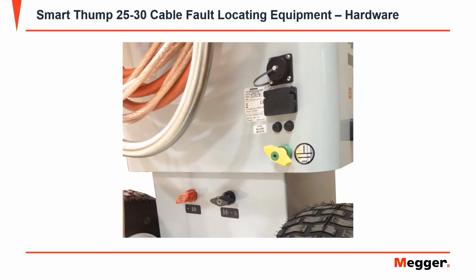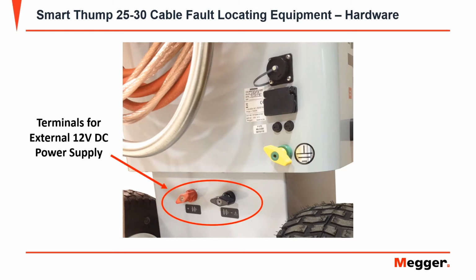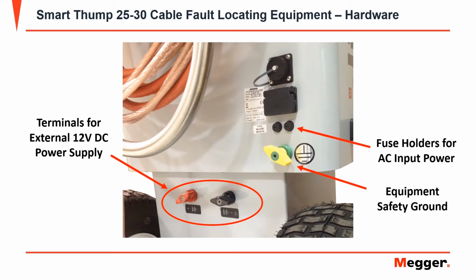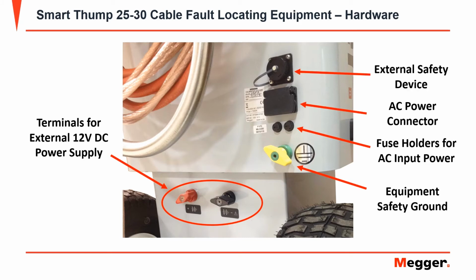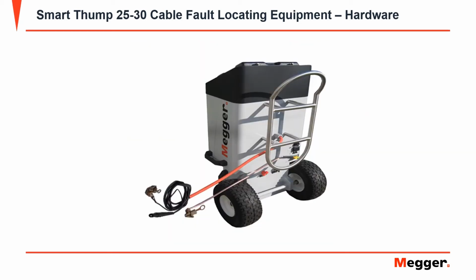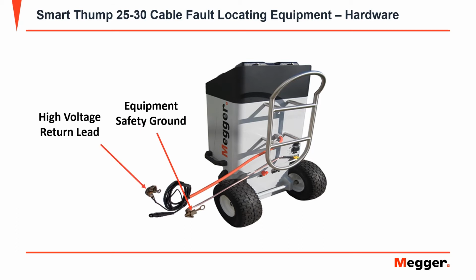On the back of the Smart Thump 25, you have terminals for external 12-volt DC power, your equipment safety ground, a fuse holder for the AC input power, your AC power connector, and an external safety device. Also equipped on the Smart Thump 25 are your equipment safety ground, your high voltage return lead, and your high voltage output lead.